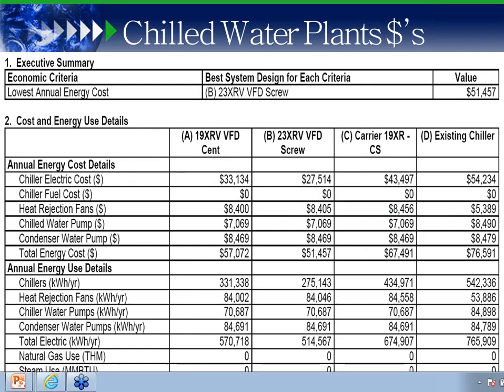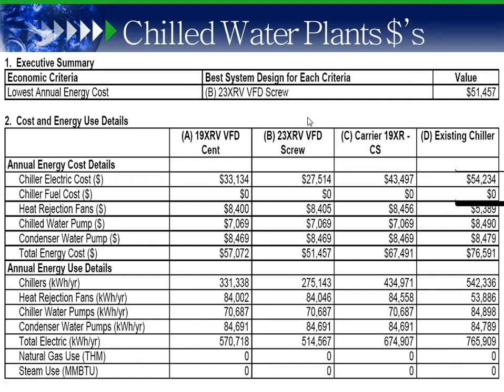So now I have my old R11 plant, which was operating and costing about $76,000 a year to operate. I now change that one chiller to a 19XR constant speed going right to left. It cost $67,000 to operate. I have a 23XRV, which cost $51,000 to operate, and I have a 19XRV, which cost $57,000 a year to operate. So I'm saving approximately $25,000 a year by changing out a chiller that has to be changed out, right? So it has to be changed out, and when we look at the next slide, the 23XRV is obviously the lowest life cycle cost chiller.